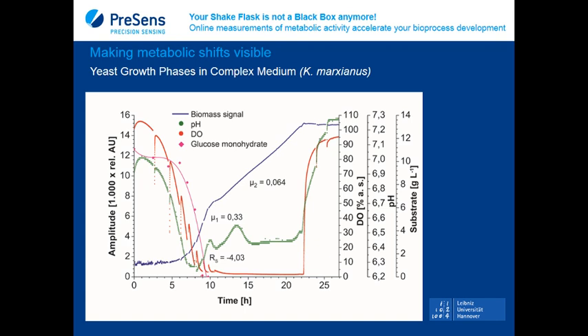Let's again have a look at the monitoring that was applied. We see our online measurement of biomass, pH, and dissolved oxygen, as well as the offline measurement of glucose. Again, here we can clearly distinguish two different growth phases when cultured with glucose as a substrate in this shake flask. In the first phase, shown here, glucose is metabolized under aerobic conditions, and the oxygen content decreases continuously down to a very low level, below 5% air saturation.